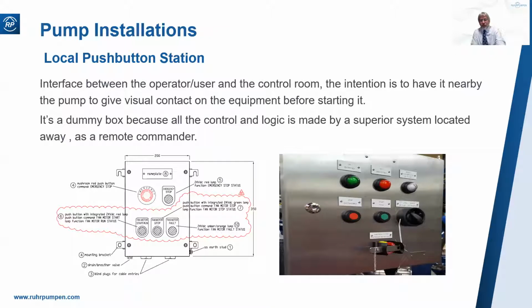Now, we don't often supply these, but some customers ask for a local push button station. There's no standard design, so they really need speccing up properly to tell us what you want them to do. Generally, the intent is to have something nearby the remotely controlled pump to give visual contact on the equipment before starting it and to instantly shut it down in an emergency.